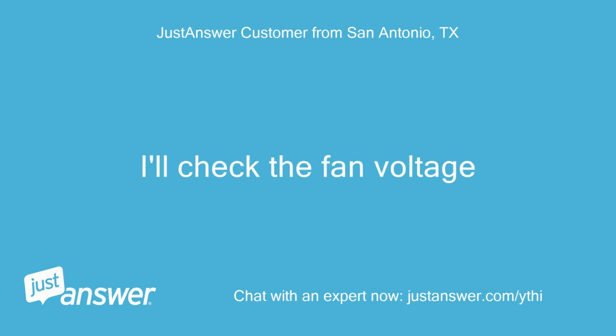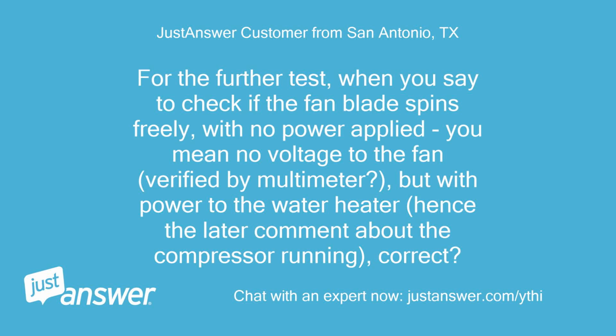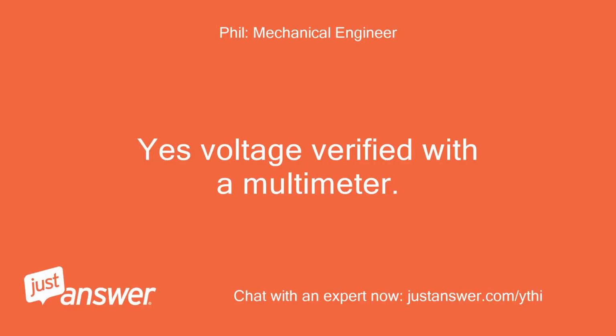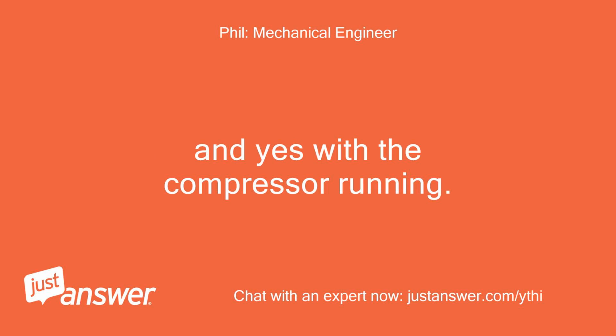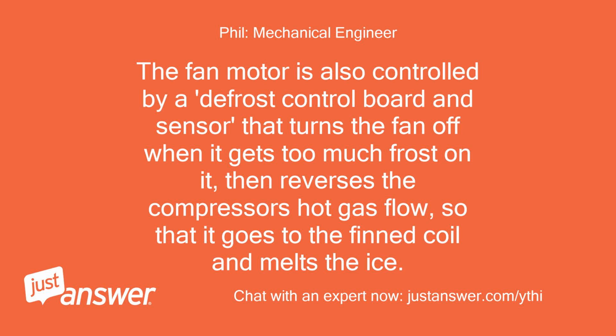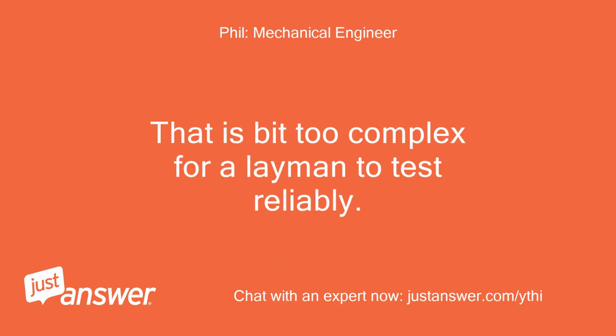I'll check the fan voltage. For the further test, when you say to check if the fan blade spins freely, with no power applied, you mean no voltage to the fan, verified by multimeter. But with power to the water heater, hence the later comment about the compressor running, correct? Yes, voltage verified with a multimeter. And yes, with the compressor running. The fan motor is also controlled by a defrost control board and sensor that turns the fan off when it gets too much frost on it, then reverses the compressor's hot gas flow, so that it goes to the fin coil and melts the ice. That is bit too complex for a layman to test reliably.